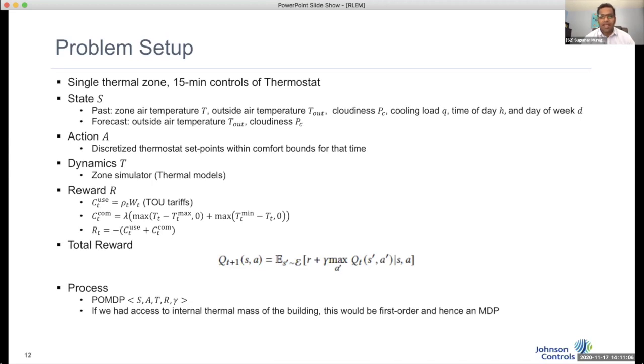With this state, the action is that we discretize the set point axis within the comfort bounds. Every time slot has a comfort bound: during occupied periods, comfort bounds are 22 to 24 degrees Celsius, whereas unoccupied is 20 to 26. So we discretize those axes, and thermostat set points are based on that axis.